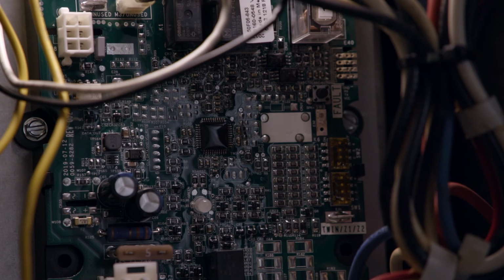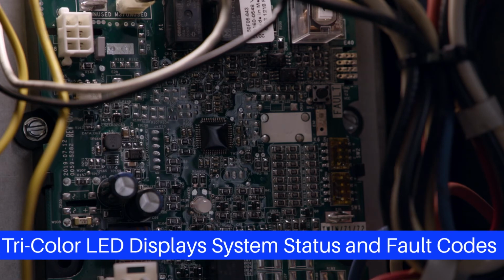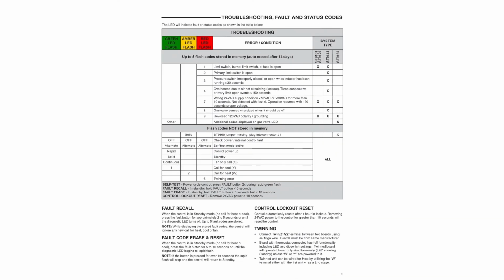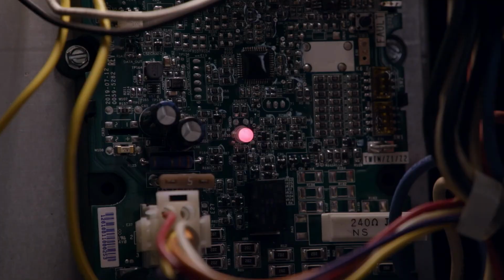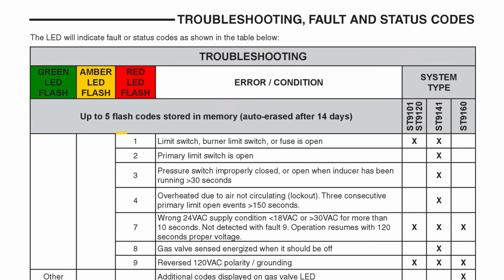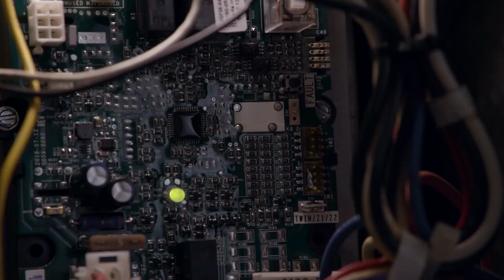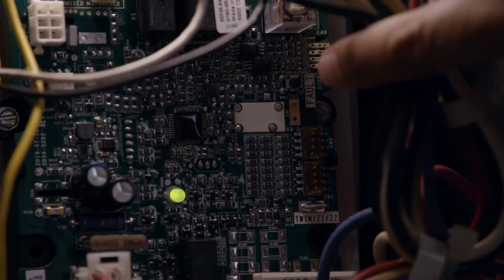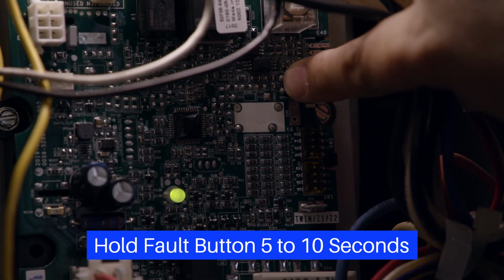To verify proper ignition, make a call for heat. The LED will flash 2 amber flashes. The tricolor LED conveys system status and fault codes. If any faults occur during the cycle, a flash code will indicate the fault. Refer to the troubleshooting label for diagnosis. The LED is displaying 1 red flash, so the troubleshooting label indicates the limit circuit is open. To prepare for operation, the fault codes can be erased by holding the fault code button for 5 to 10 seconds.